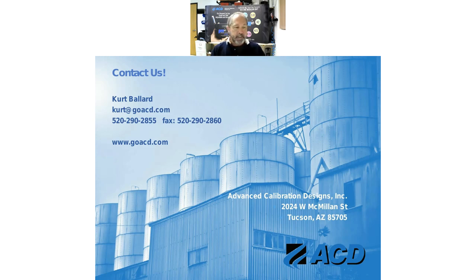The same thing happens on the generating sources. If the electrolyte level drops down too low, or if the generating cell is not placed into the instrument correctly, the instrument is looking at it, and it's also looking for resistance on that cell. If any of those things happen, it'll say source failure or no source found, and it'll eventually shut itself off so that you don't have an inaccurate calibration. Okay, very good.